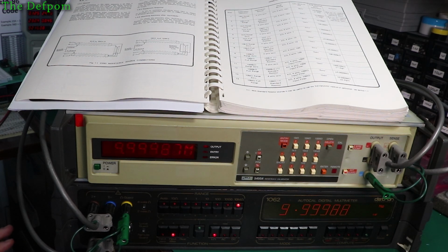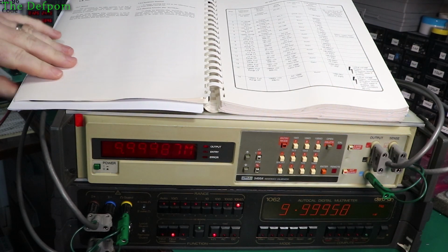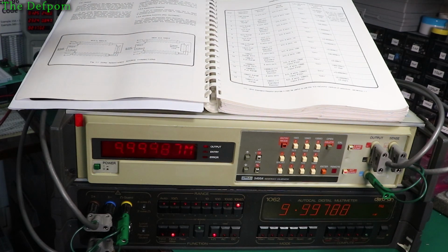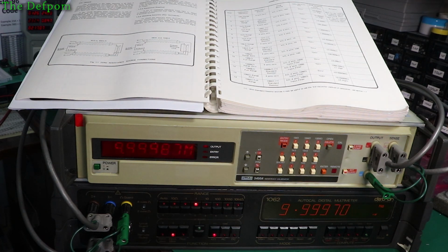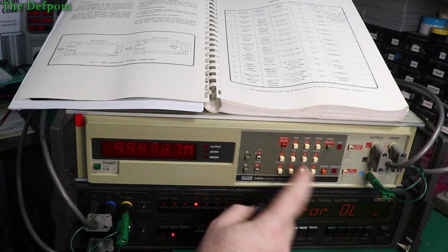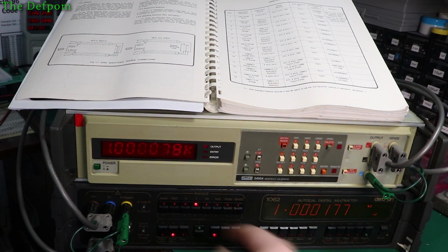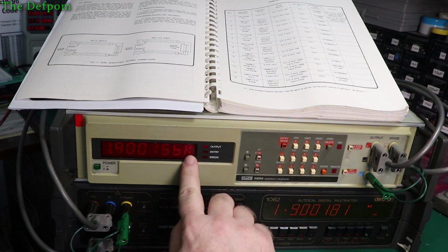Yeah, okay, so that's that one. So that's all the ranges calibrated. That is the completion of that calibration. That's the ohms done. So what I could actually do now is, if I go to the 1K range, chuck in 1K. We should get 1K as per this, pretty much, once it settles. So if I do 19, what do we get? It's slightly out, so the actual scaling is a bit different, which is the interesting part here.